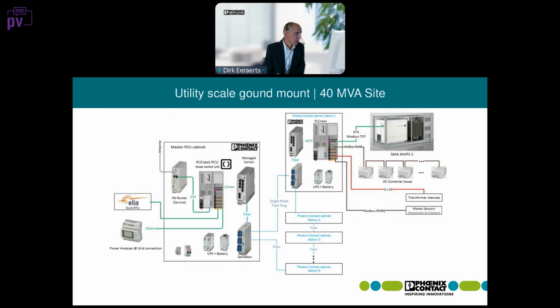Another example is a large ground mount site where we have 9 stations that are very similar. So you see a station on the top right with our control cabinet, and then connected to that the inverter, the combiner boxes, then transformer alarms and meteo sensors. This complete setup is repeated 9 times, and all the PLCs are linked in a fiber ring.